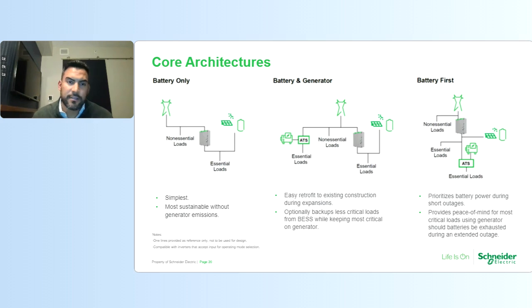So in this case, both the ATS and the automatic interconnection switch here are independent. Picture a main switchboard, and the ATS is downstream as well as an interconnection device. And both of them will operate independently. So upon an outage, the ATS will transfer to the generator and its respective loads, and the automatic interconnection switch will also disconnect, enabling the energy storage system to provide power to its own respective loads. And I'll go through this animation. It just shows you there's different ways to configure a single line diagram to have your energy or your microgrid system provide backup power.